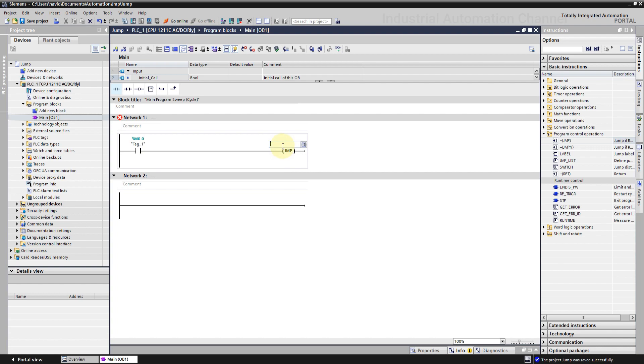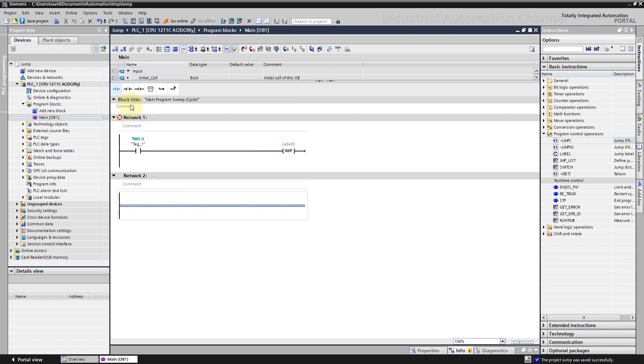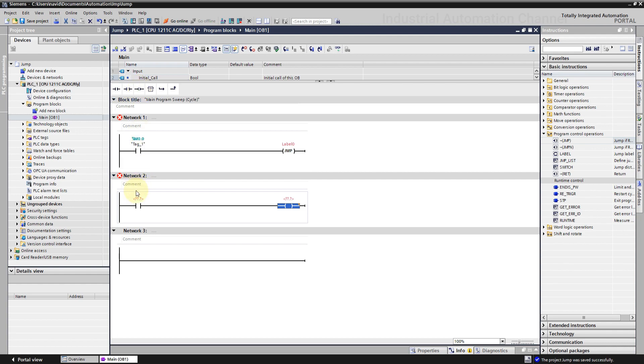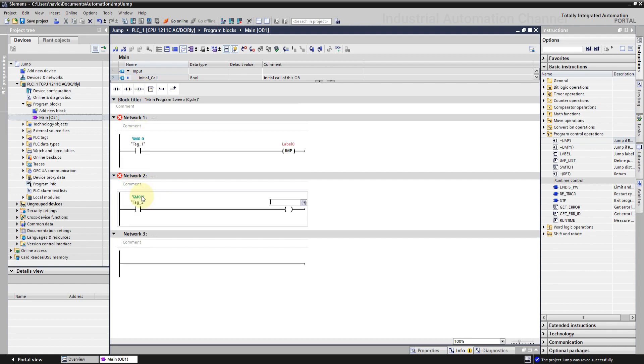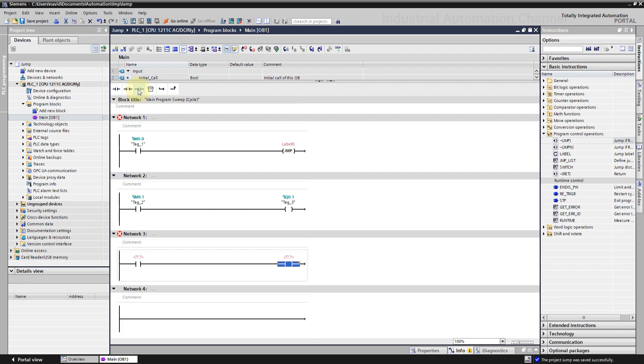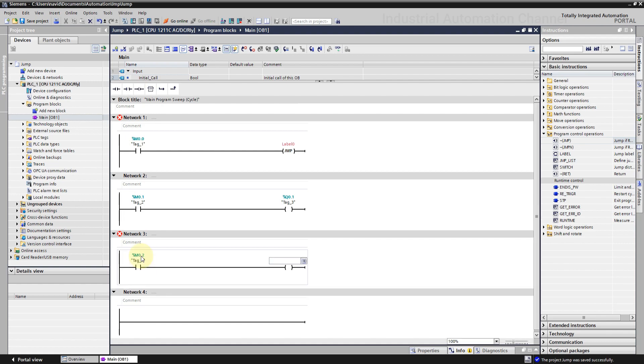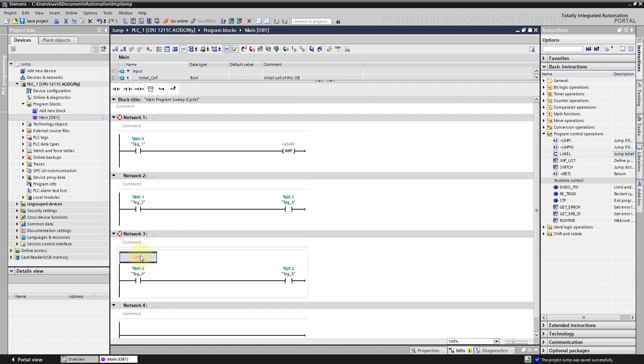It needs a label to jump to when it's activated. Currently it's red because we have not yet defined the label at any network. I will define it inside the third network. Second network with a contact and an assignment. Next network again a contact and an assignment. But I want to jump here when the jump instruction is activated. So I need to define a label in this network. Drag and drop label to the network. Write any name that you want. But it must be the same over the jump and here inside the label.